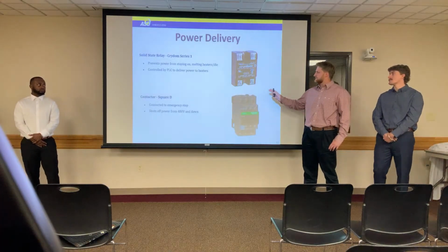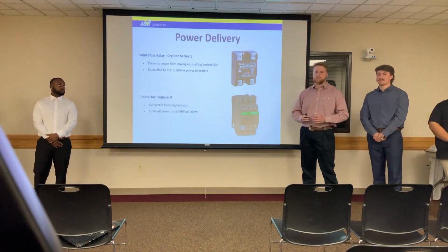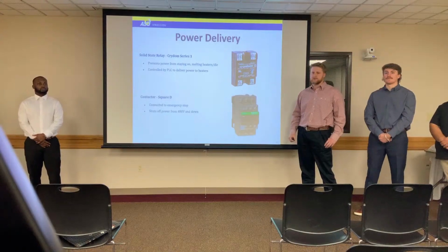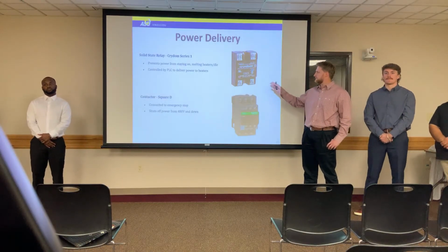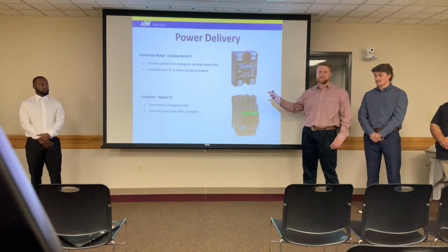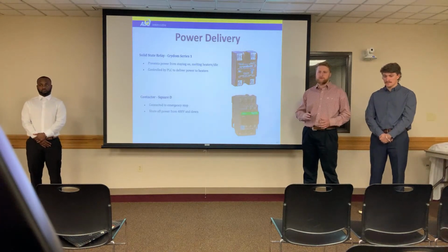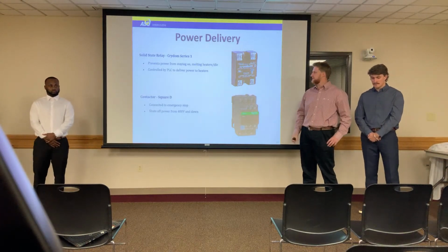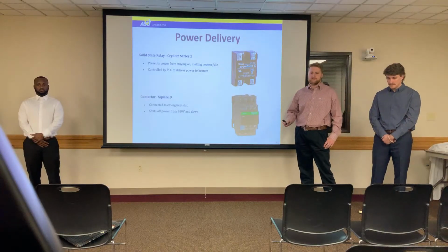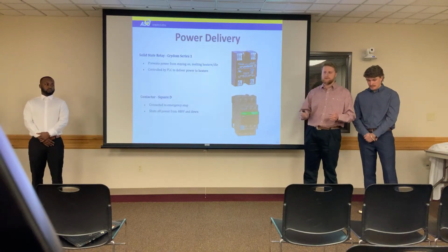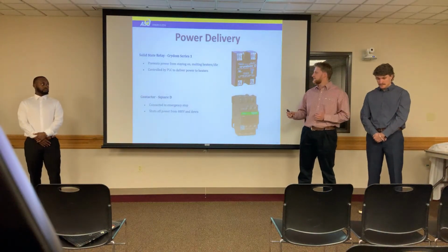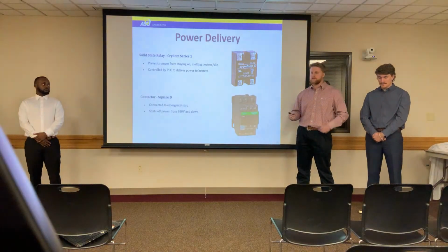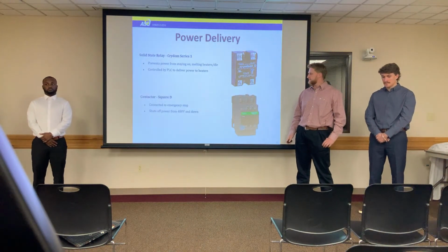So we're also using solid state relays. These are basically power switches which are used to control the heaters. So the PLC plugs into the solid state relays, and controls that 240 volts being switched on and off for the heaters. And that PLC reads temperatures from our thermometers and the die, and will switch on and off the solid state relays which control the heaters.